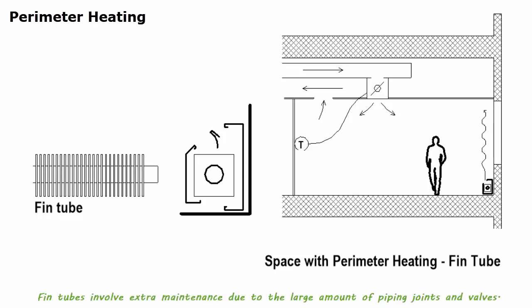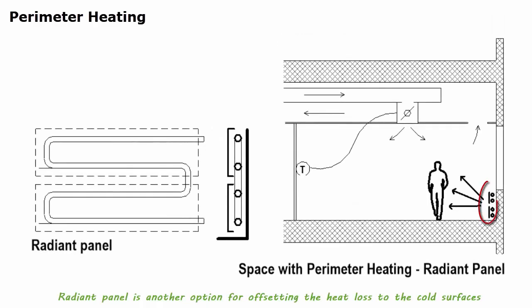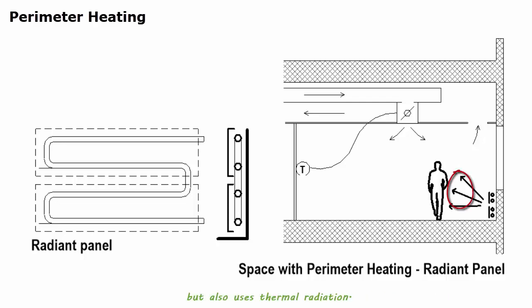Fin tubes involve extra maintenance due to the large amount of piping joints and valves. They may also be in the way of system furniture in offices. Radiant panel is another option for offsetting the heat loss to the cold surfaces of walls and windows on the perimeter of a building. A radiant panel not only uses air as a medium for heat transfer via convection, but also uses thermal radiation. Both fin tubes and radiant panels help control condensation, typically found on large exterior glass walls.